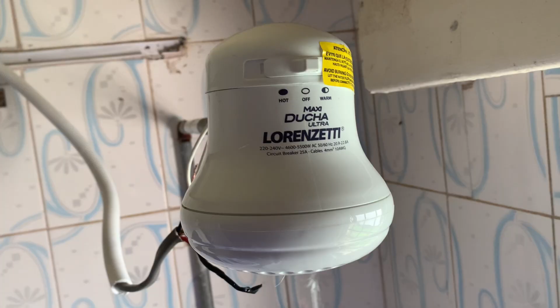Have one instant shower head supplied by these wires: the neutral, the earth, and the live connection. Each of these wires is rated at 4.0 millimeter square, which is the cross-sectional area of the wires themselves. The insulation of these wires is a perfect consideration because they carry a lot of current supplying an instant shower head, which is basically a heater.